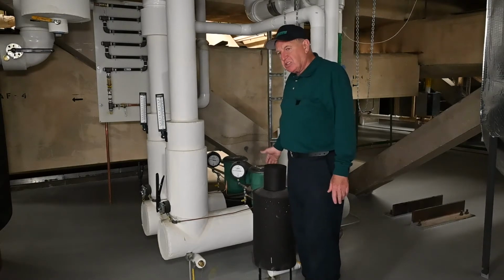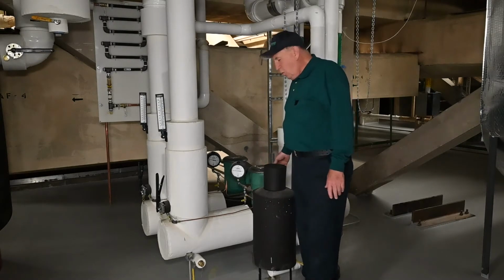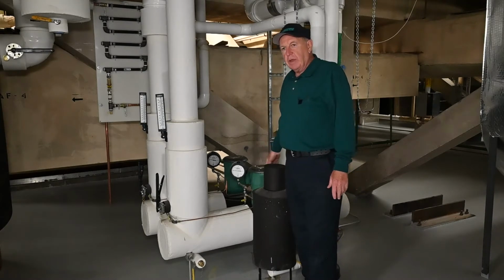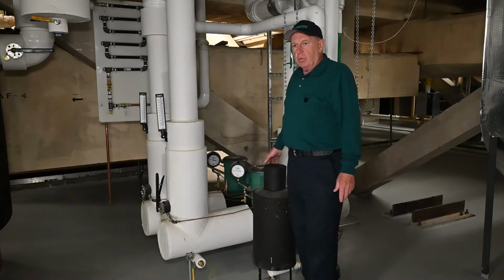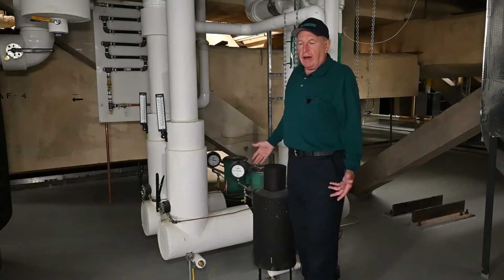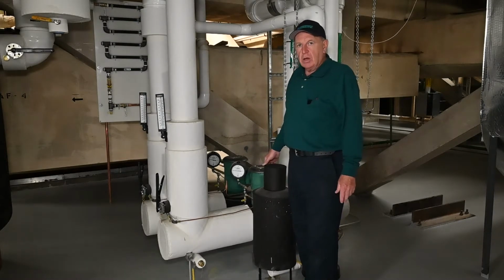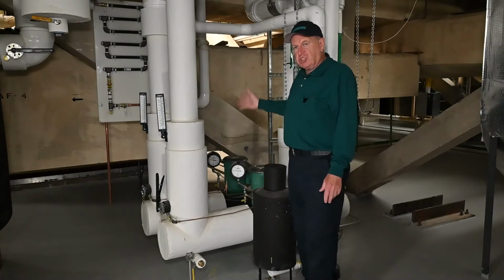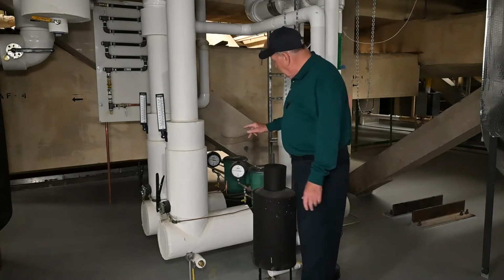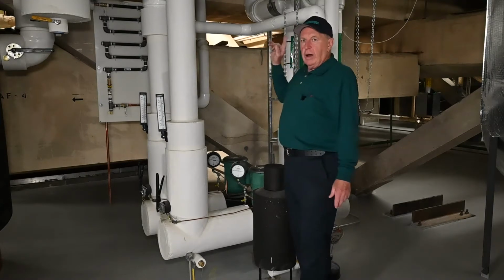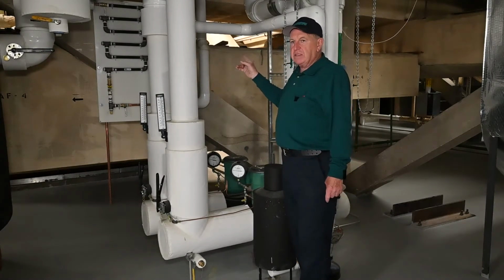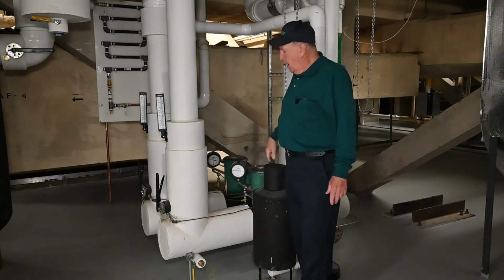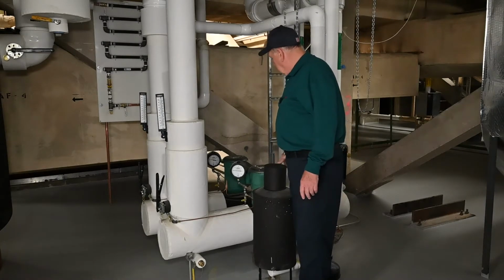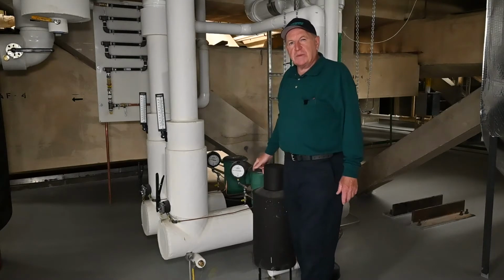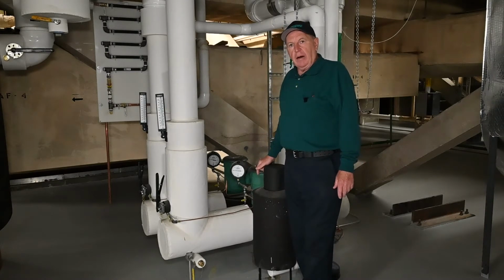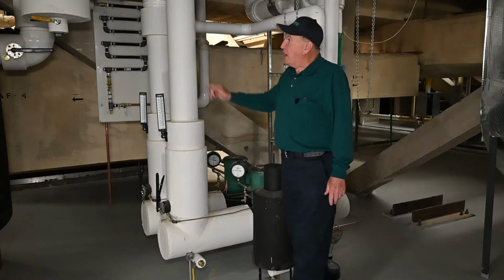There's complete redundancy, so there's two pumps, each one sized big enough for the chiller. The minimum speed of the pump will be enough that the chiller gets its 118 gallons flow, so the minimum speed of the pump will match the chiller minimum flow. These pumps pump through a dedicated chiller that feeds a dedicated air handler for the Rare Books. They have a 30% glycol mix, and they go through an air separator right here.